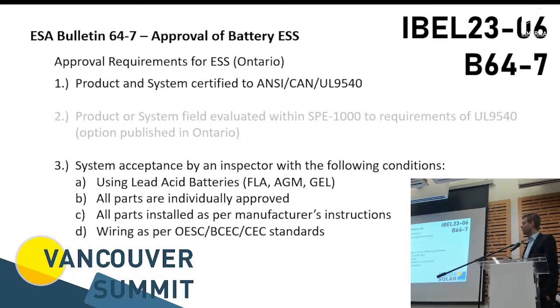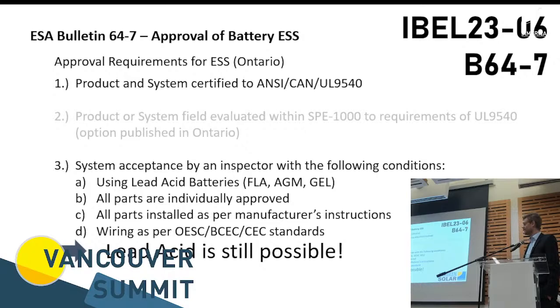At that point, all individual parts need to be approved. So instead of a system certification, you have to have a certified inverter, a certified rack, or a certified transfer switch, and then you put that all together. The wiring and everything has to be according to code in your specific jurisdiction, and your inspector will go through the single components to then say, okay, I follow the second variance that is offered with that lead acid chemistry. And that is the main message.